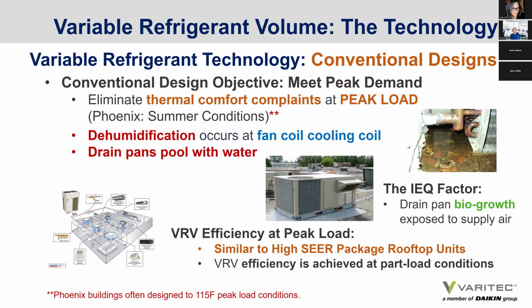So a conventional way of designing variable refrigerant is to provide untempered outside air to the VRV system and then design to the peak load, to the peak summer design condition. And we have to realize that the dehumidification would then occur at the variable refrigerant fan coil unit as well. And if it's doing its job, and it can, it will be filling drain pans with water at the fan coil units within the space. So the problem is that when these units operate at peak load and at max load, they're no more efficient than a high SEER package rooftop unit. So we're not getting the full advantage of a variable refrigerant system when we have unconditioned outside air, and the outside air is being co-treated with the return air to each zone.